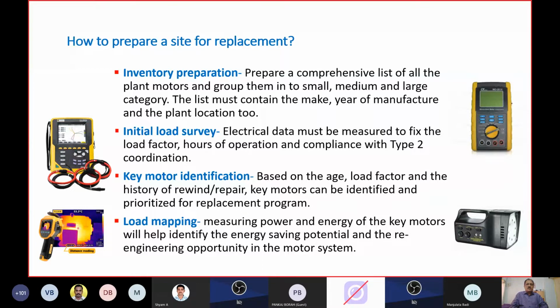Then we carry out an initial load survey. For this, our people need not go. Auditors need not come from outside. Industry plant engineers can carry it out themselves. While doing this exercise, we also recommend them to prepare another Excel where they will work out the load factor, number of hours of operation, and type 2 coordination, which typically talks about the protection control circuit available for the motors. In each motor starter box, what is the contactor, relay, or any other protection cable, they can be listed, and then compared with the standard IEC standard available in order to either improve or replace the existing control protection circuits.